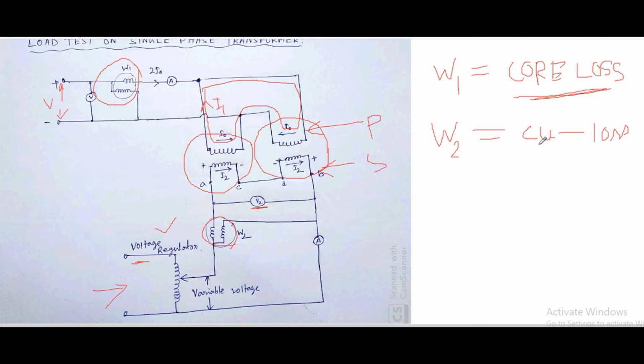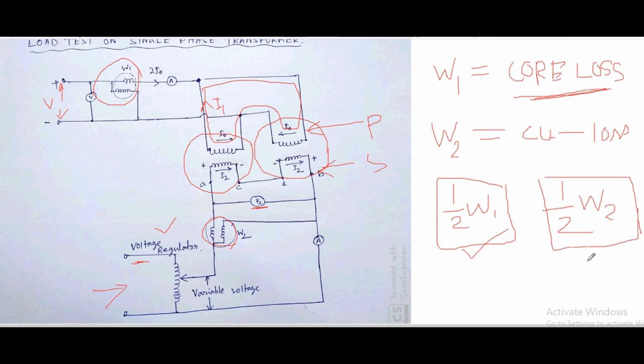So when we know the core loss and copper loss, and this core loss is for these two transformers, that means transformer 1 and transformer 2, each transformer's core loss will be half of the W1 wattmeter reading, and each transformer's copper loss will be half of the second wattmeter reading, W2. This is each transformer's core loss and each transformer's copper loss. And if you know the core loss and copper loss, we can easily calculate the efficiency.